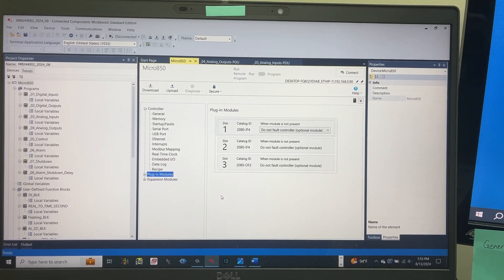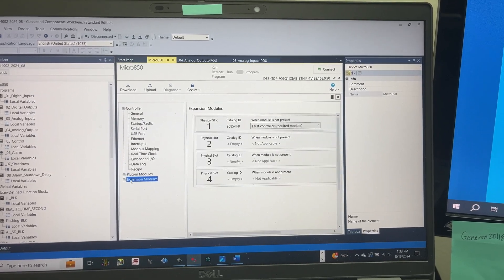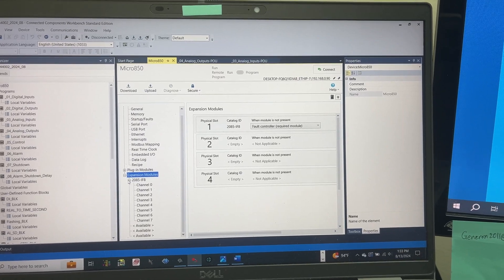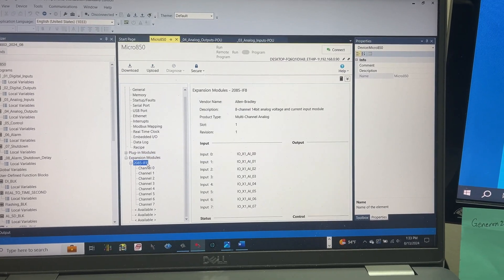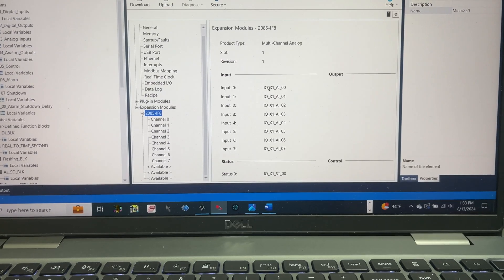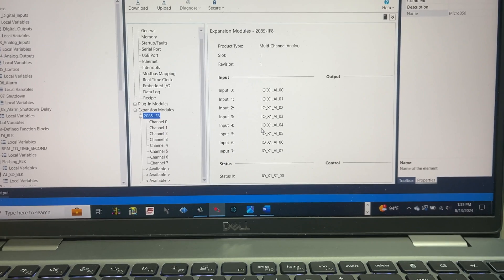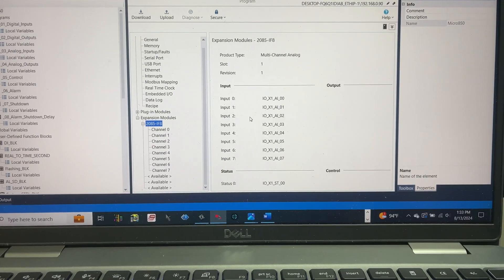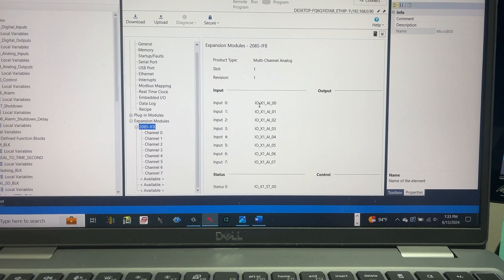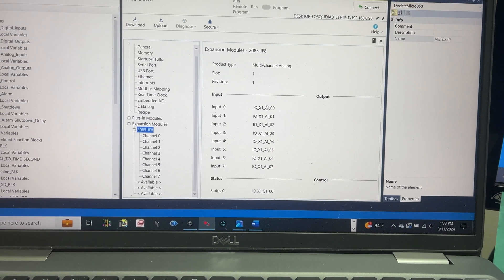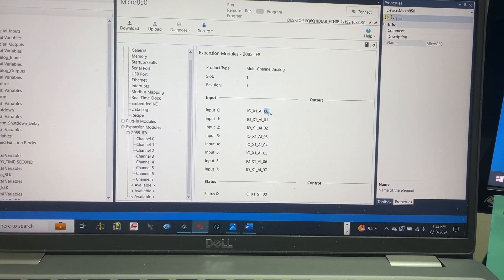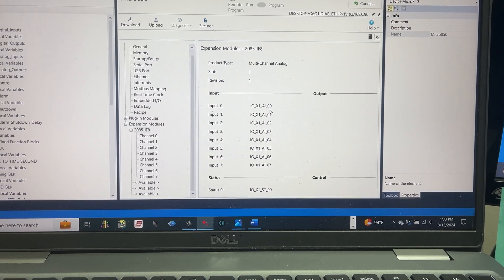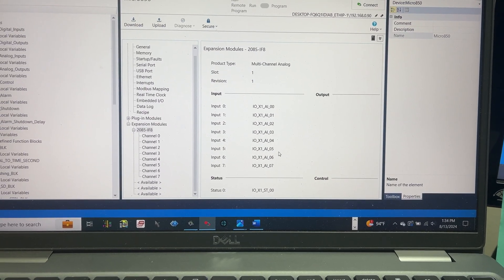In Connected Components Workbench, this is the configuration for the expansion module 2085-IF8. These are the PLC tags for the actual analog inputs from the expansion module: I-O for I-O module, X1 for expansion module 1, AI for analog input, and the two digit number is for the channel number. It goes from 0 to 7 for the 8 channels.